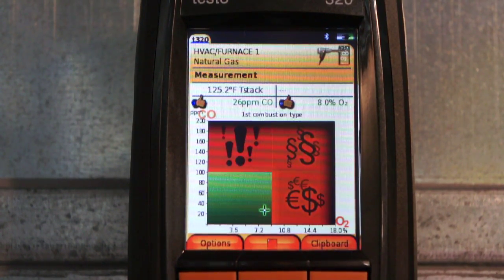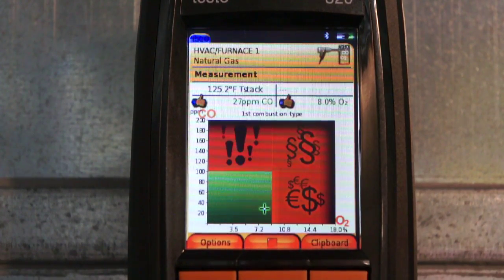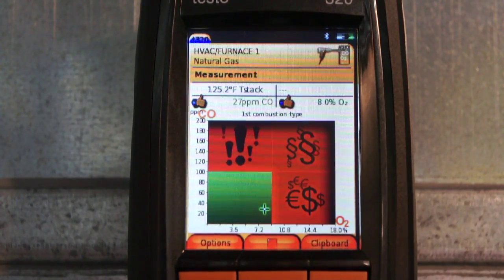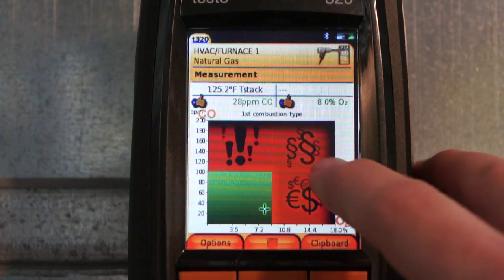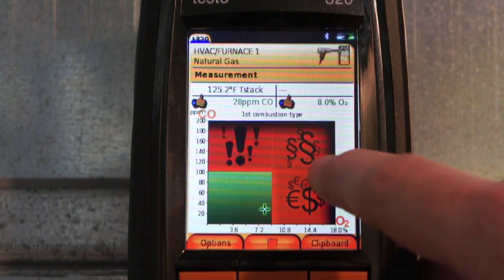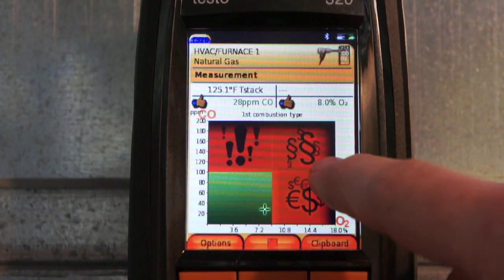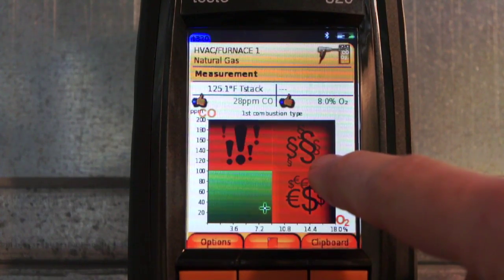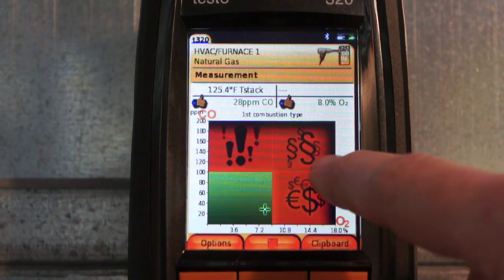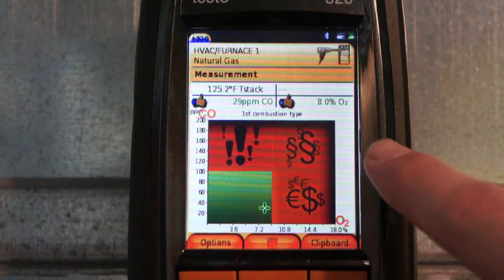We're talking a commercial burner, we might run that down as low as 10% excess air in ideal, where we have an application we're going to test it a lot and keep on top of it. But for a residential appliance, 50% excess air is pretty typical where we want to run. If we're up here in the infinity symbol zones, I'm not sure what that symbol is for. Obviously we have too much air and we have too much CO, and this is not the area at all we want to be into.